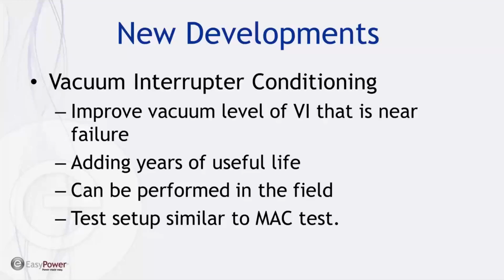And so we found that we can take a vacuum interrupter that is very near failure and bring it down to somewhere near midlife, which is equivalent to adding somewhere between 5 and 10 years of life to these vacuum interrupters. Right now, we're in the middle of a few case studies on this, with our local utility and some other large factories that use many of these vacuum interrupters. And so this vacuum interrupter conditioning can be applied to any vacuum interrupter that can be MAC tested. So if a MAC test can be performed on the vacuum interrupter, then this vacuum interrupter conditioning can also be performed on the vacuum interrupter.